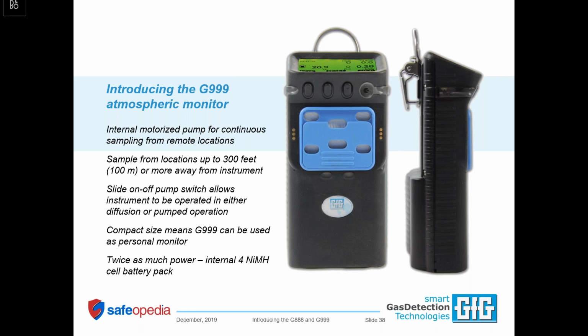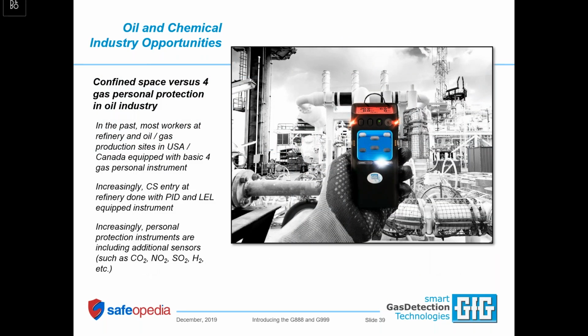Compare that to several excellent products from our honored competitors, like the Altair 5X from MSA or the MultiRAE product line — you don't really have the option of turning that pump off when you don't want it. It runs all the time, which shortens the operating time per charge if you don't need to run the pump continuously while using the instrument. That's a tremendous advantage.